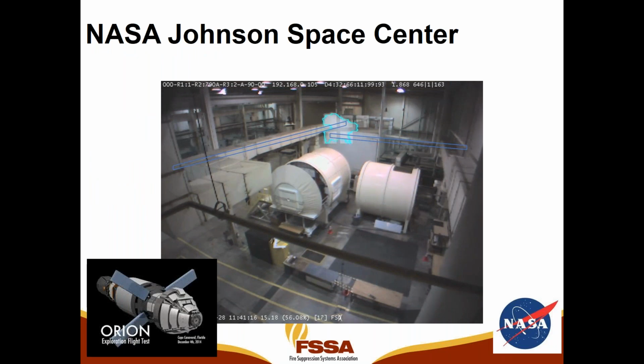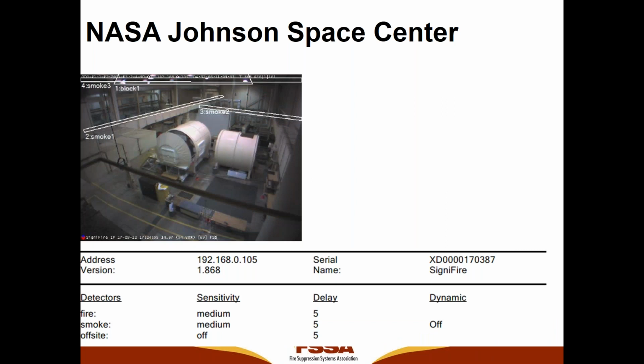This is an example of zone use. This is the Orion spacecraft in Houston. This is a mock-up, actually. The entire warehouse was covered by video analytics cameras. A smoke emitter was lit on the far side of the module. The smoke rose. As soon as it hit the zones, it went into alarm.